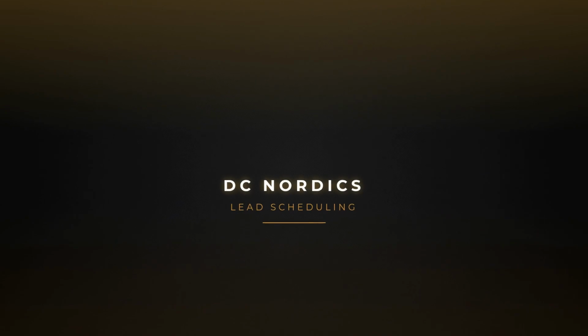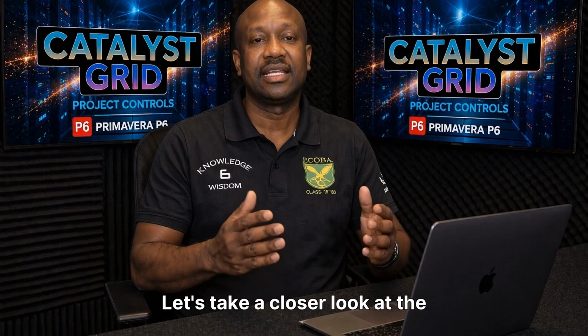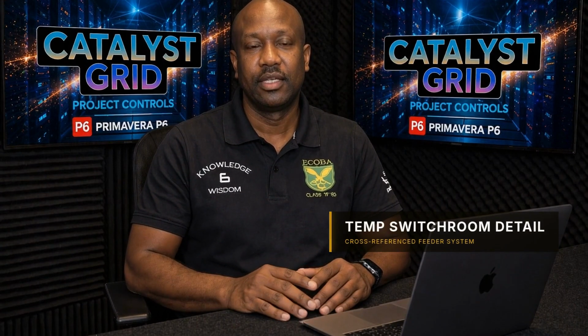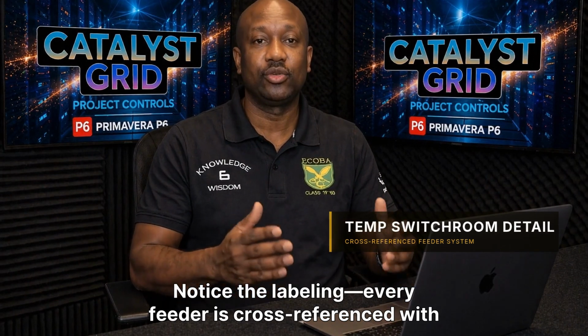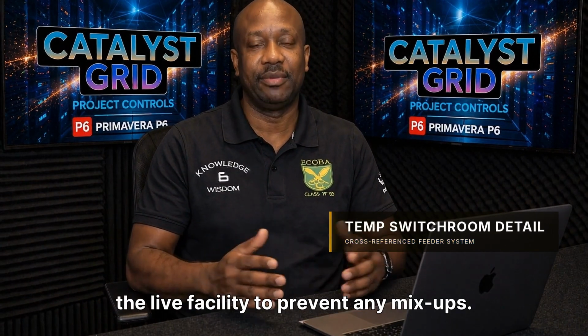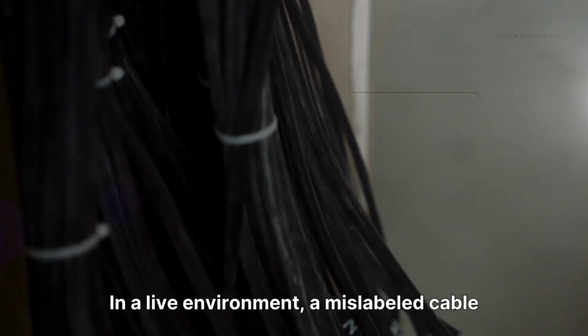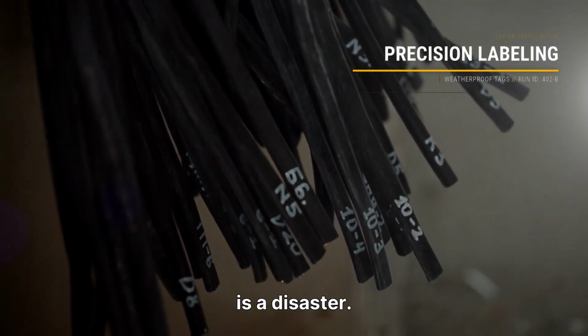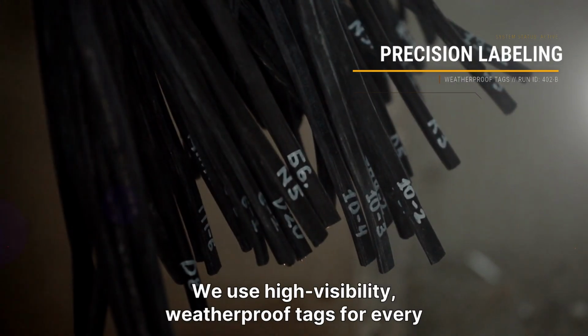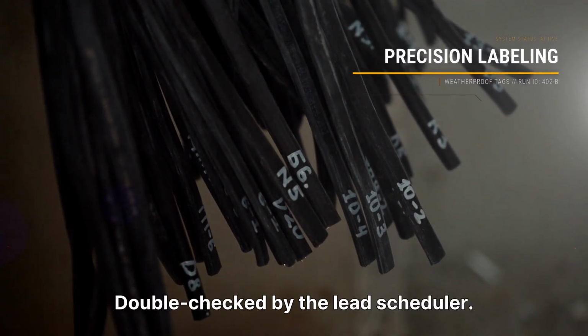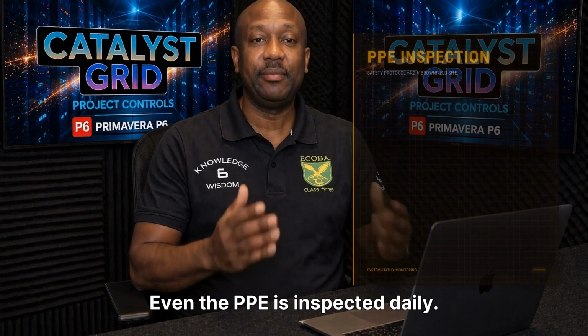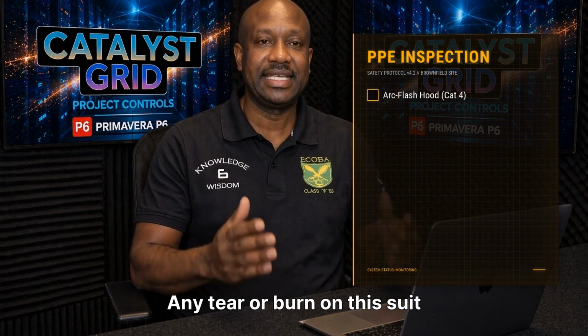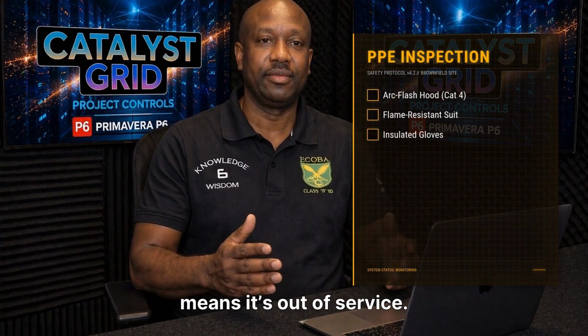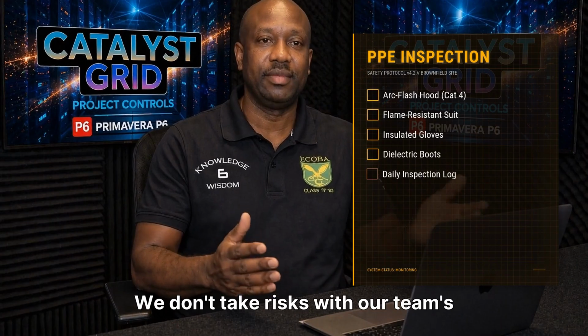Let's take a closer look at the temporary supply. Notice the labeling. Every feeder is cross-referenced with the live facility to prevent any mix-ups. In a live environment, a mislabeled cable is a disaster. We use high-visibility, weatherproof tags for every single run, double-checked by the lead scheduler. Even the PPE is inspected daily. Any tear or burn on this suit means it's out of service. We don't take risks with our team's safety.